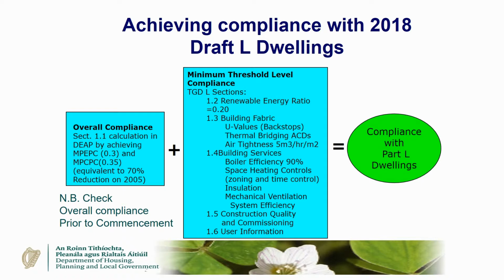Thermal bridging: there's guidance on thermal bridging, and the acceptable construction details are available. The other change we've made to Part L is we've advanced the air tightness from 7 metres cubed per hour per metre squared to 5 metres cubed per hour per metre squared. We have minimum requirements for boiler efficiency and mechanical ventilation system efficiency. We also have a requirement for construction quality and commissioning, and, more importantly as buildings become more advanced, for user information. When you show overall compliance in DEAP, and when you meet all the minimum threshold levels, including renewables, building fabric, building services efficiency, and handover information, then you've achieved compliance with Part L of the building regulations.